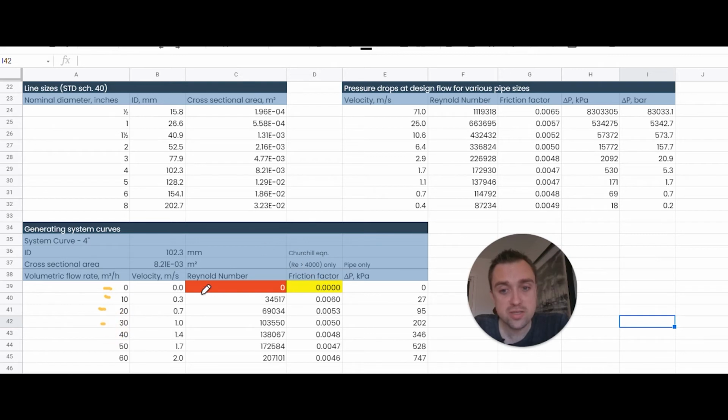So the equations I'm using over here are identical to what I was using over here. It's just I'm varying the flow rate now. So now here I've added in a check that my Reynolds number is over 4,000, which means I can use this Churchill equation to calculate the friction factor. Of course, at no flow, there is no pressure loss, so the friction factor is zero. It's okay that it's highlighted.